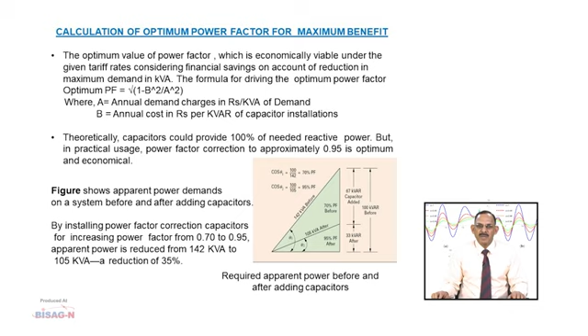Impact of power factor correction capacitors. Improvement in power factor leads to the following benefits: reduced electricity bills as well as incentive for maintaining power factor above 0.95, increased system capacity, improved voltage, and reduced energy losses. Reduced electricity bill. The electric supply company, that is distribution company or state electricity boards, provide working power in kilowatt as well as reactive power in kVAr in the form of apparent power kVA as per station load, that is according to connected load or contracted maximum demand.